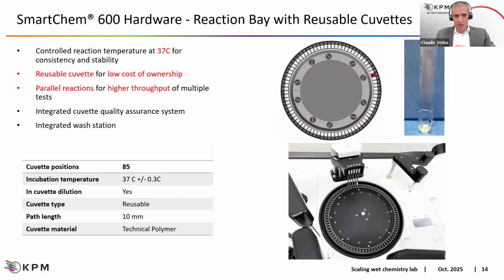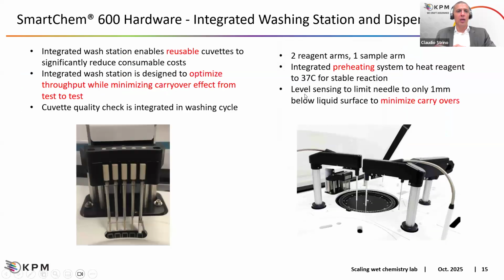And this is a really important feature we have. So with the reusable cuvettes, because we have a reaction plate incubated at 37 Celsius degrees, the temperature is stable and the same for all the reactions. We have reusable cuvettes for very low cost of ownership, parallel reactions for high throughput of multiple tests, and when washing the cuvettes, the quality of the cuvette is automatically checked and verified at the end of each wash. Really, one of the big points when using reusable cuvettes is that the efficiency of our washing station can really minimize the carryover effect from test to test.